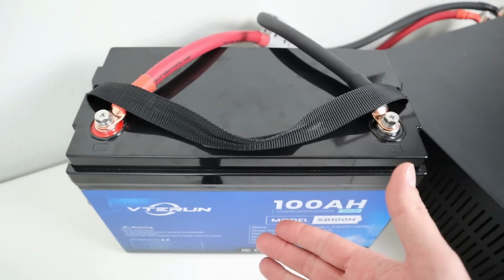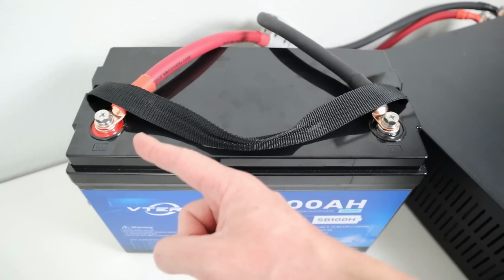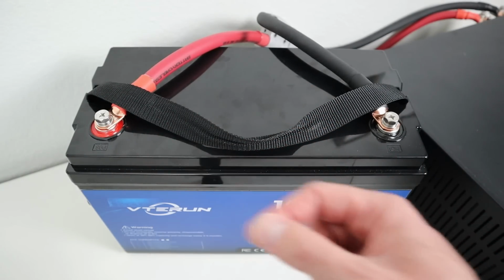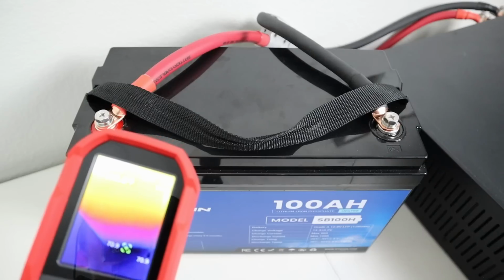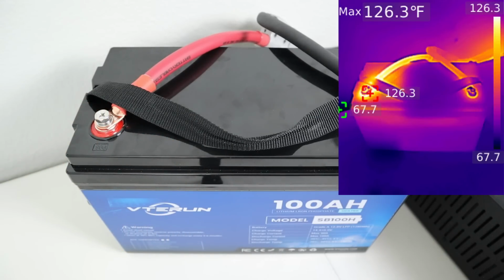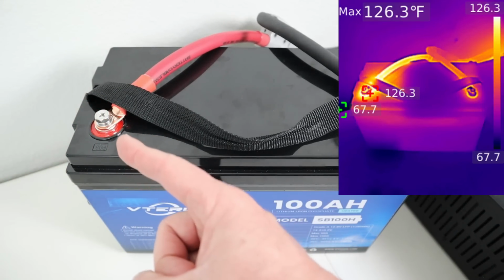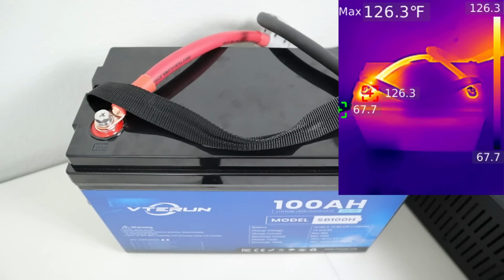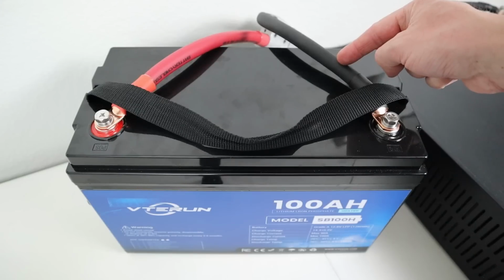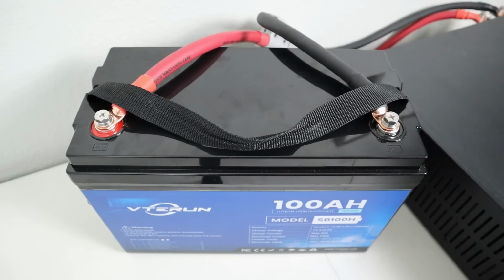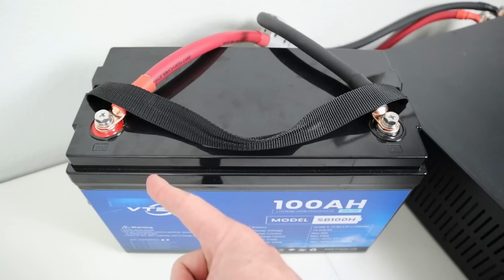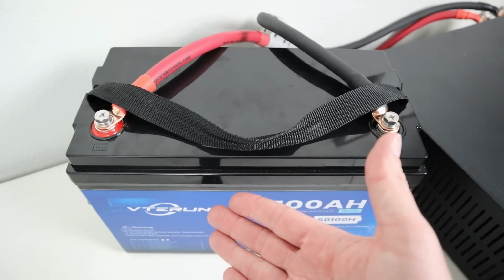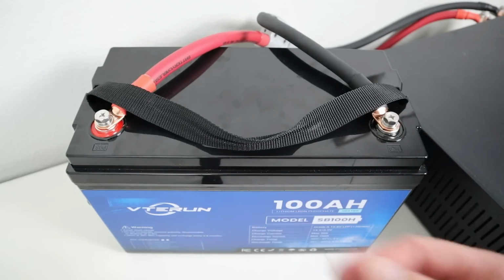Now, an interesting note here at the end of the test, I touched the positive terminal and the wire, and it was fairly warm. I measured with my thermal camera, and it was showing 127 degrees. So I'm guessing that the conductors on the inside of the battery are a little undersized for that 100 amp continuous load, because the wires that I'm using here are 1/0, and they're rated for over 150 amps continuous. So it has to be the internal wires. I'm excited to tear this open later in the video and see what they're using for that.